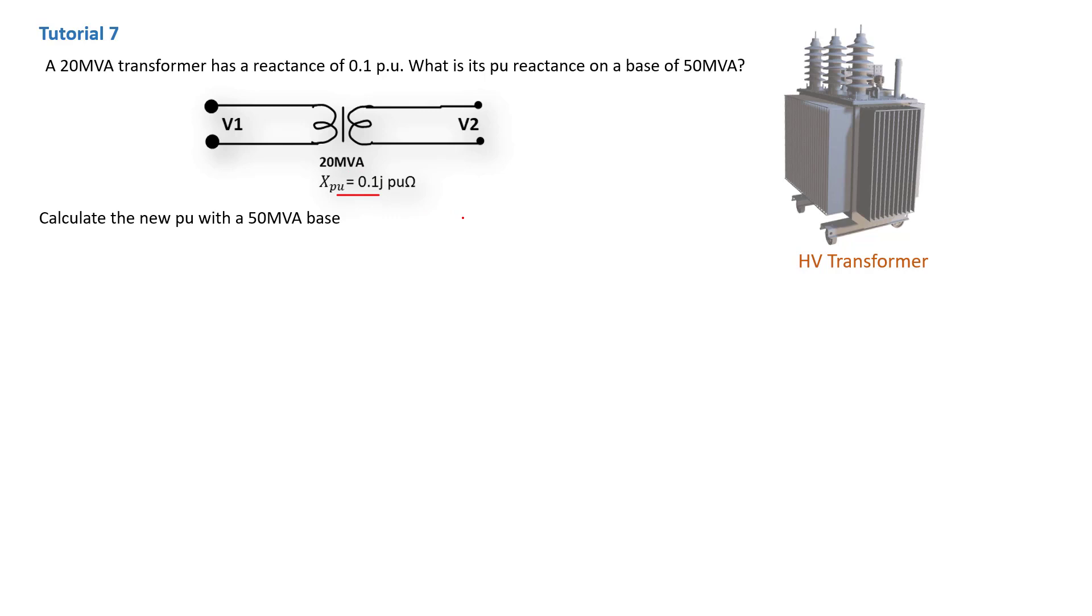But now they are asking us to determine what is its new reactance, its new per unit reactance on a different base which is 50 MVA. So this is going to be a very simple calculation.